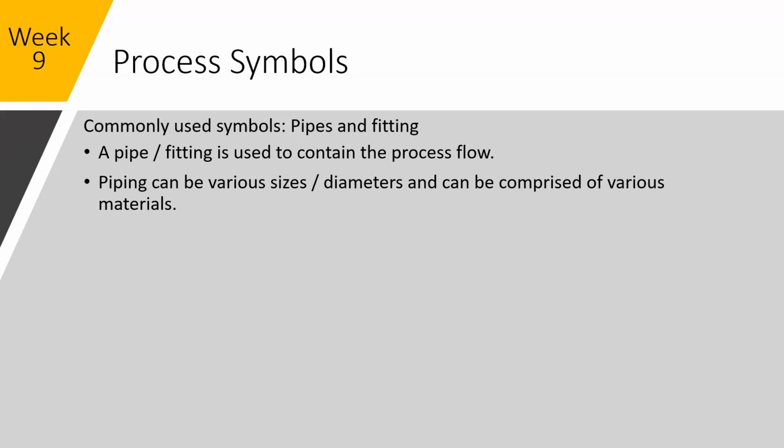An example I see a lot would be process piping, so stainless steel piping, having chlorine injected into the system. Typically, that's going to be coming from a medical tubing that would then have an injection manifold that would be ported into the side of the stainless steel piping, and then those would be mated together. So you would have the hypochlorite being run right into the center of a pipe to make sure it's getting mixed properly. Piping can be insulated or non-insulated.